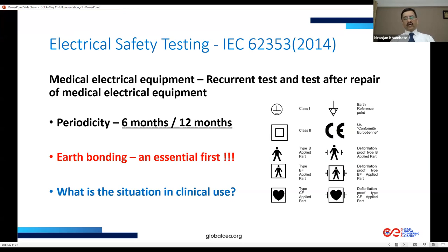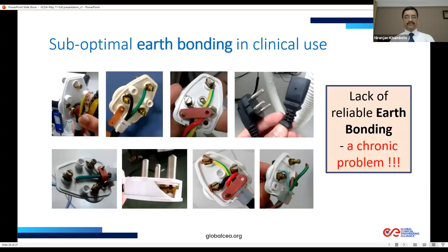We all know that earth bonding, the electrical connection to the earth of the equipment body, is one of the essential first tests in this standard. Unless we fulfill that requirement, there is no point doing any other test further. Now, does this very basic minimum requirement of earth bonding really hold good when it comes to the equipment being in clinical use? Can I have the next slide, please?